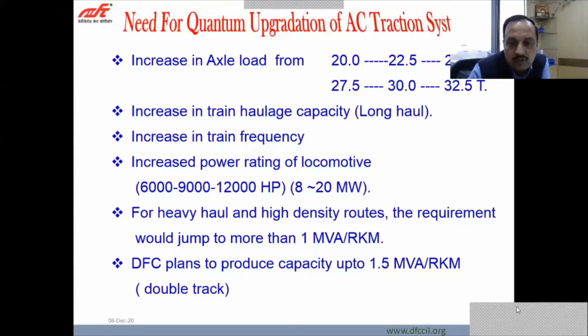If you compare with IR, the power capacity on high density routes is not more than 1 MVA per RKM. It means in 1 route kilometer, the capacity is only 1 MVA. It is even less than that. Whereas in DFCCIL, it has been planned to augment the capacity up to 1.5 MVA per RKM, which means more than 50% increment on DFCCIL.